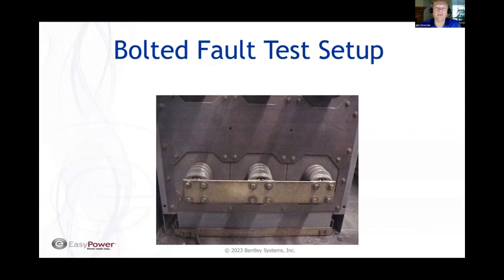Now, as an example of what this means, and this is getting a little bit into the weeds, this is a picture of what's called a bolted fault test setup. It's the way pieces of equipment are tested. Literally, the outputs are tied together with this piece of copper. It looks like it's about 3 inches wide and a quarter inch thick. And the equipment's supposed to not only survive, but interrupt the current flow to protect whatever's loaded into the equipment beside it.